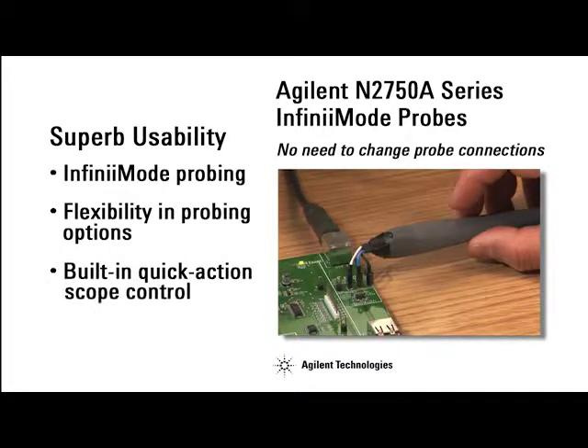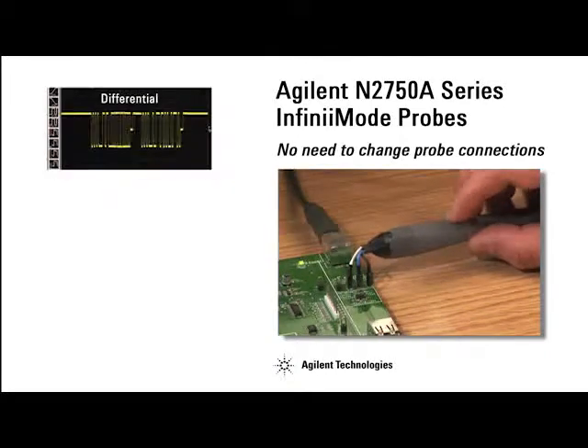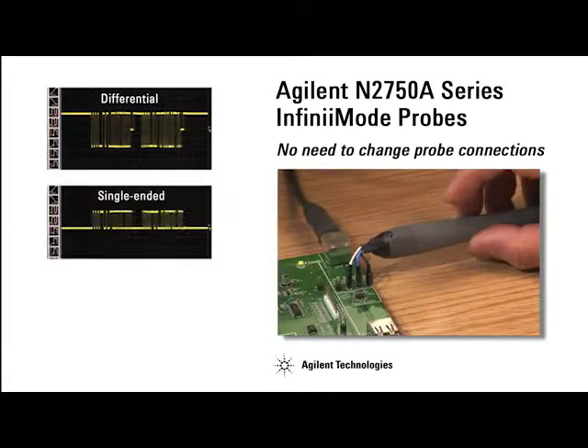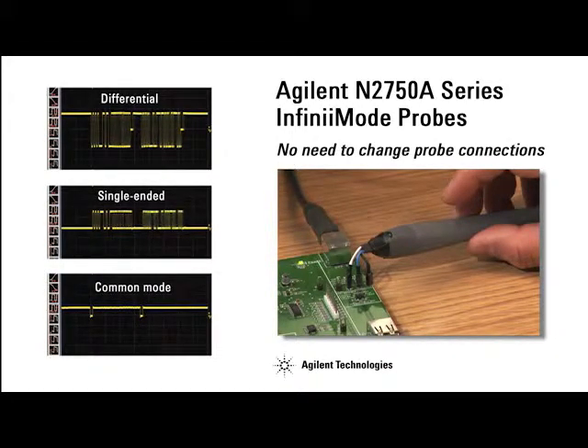Agilent's N2750A series probes come with InfiniiMode operation mode. The InfiniiMode allows convenient measurements of differential, single-ended, and common mode with a single probe tip that eliminates the need to change probe connections.